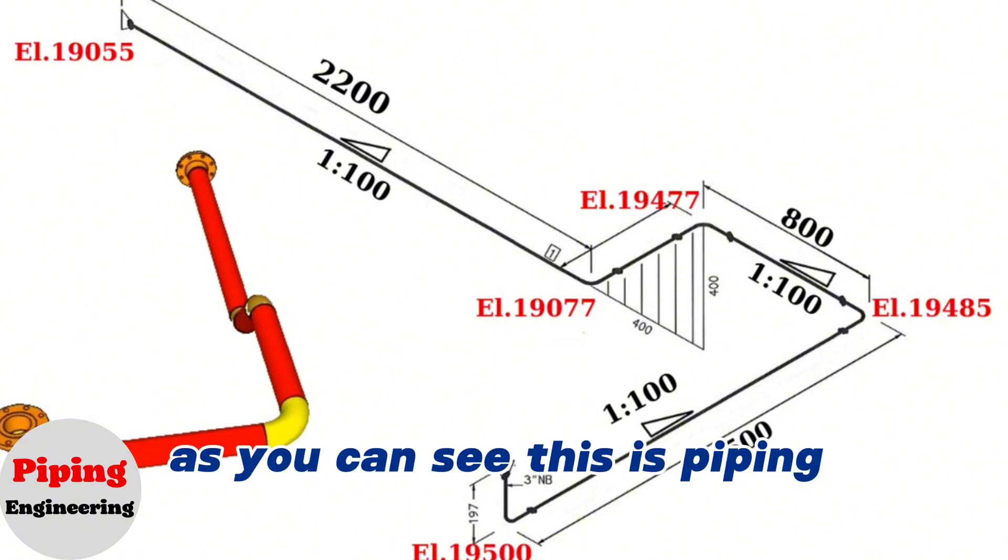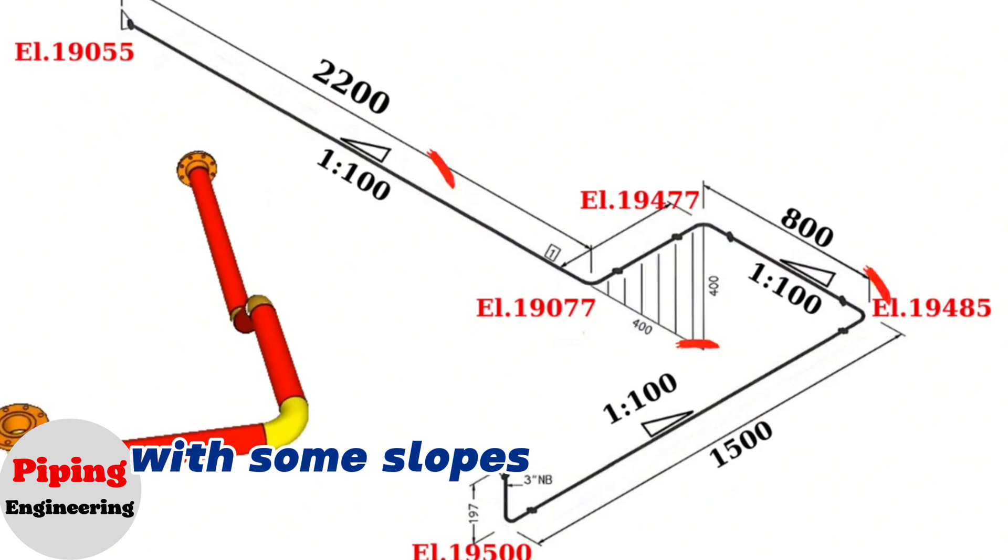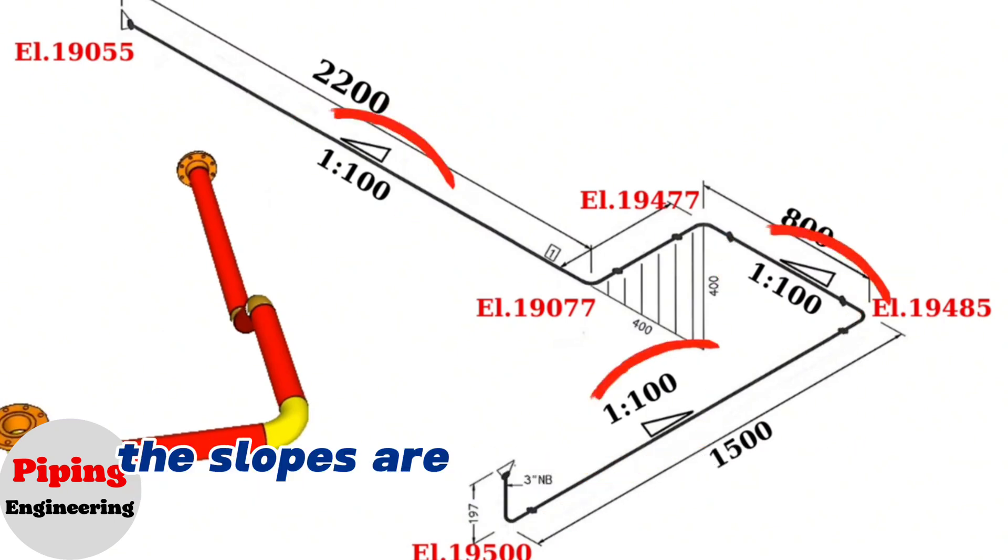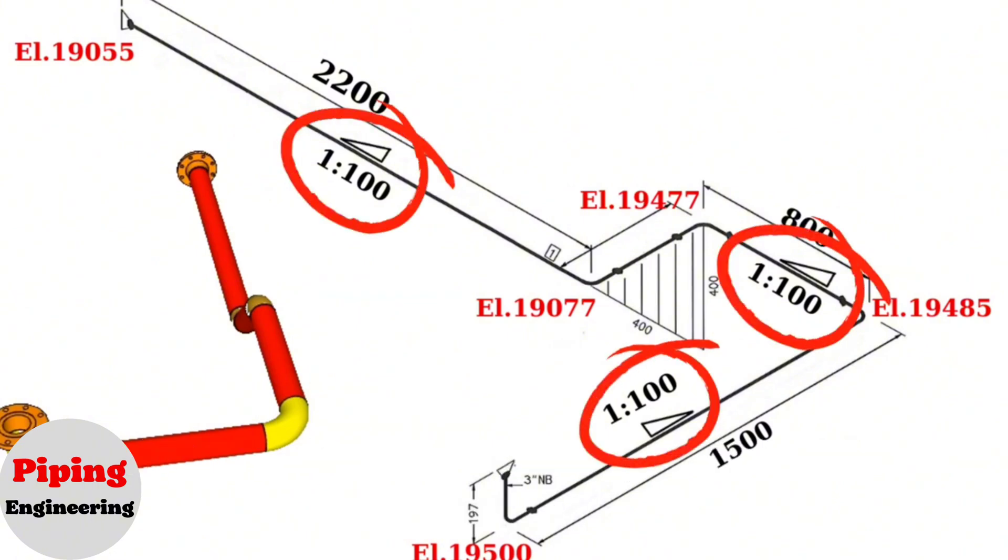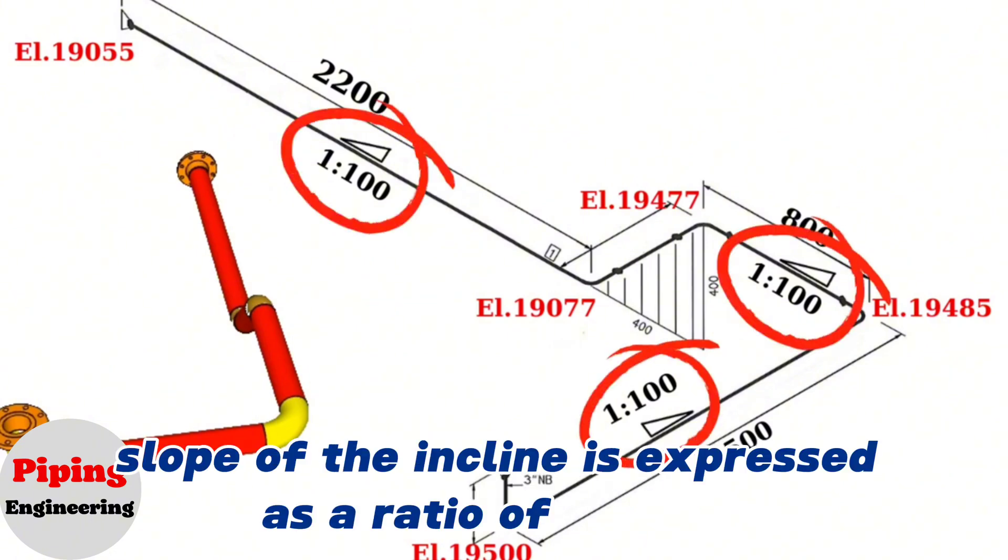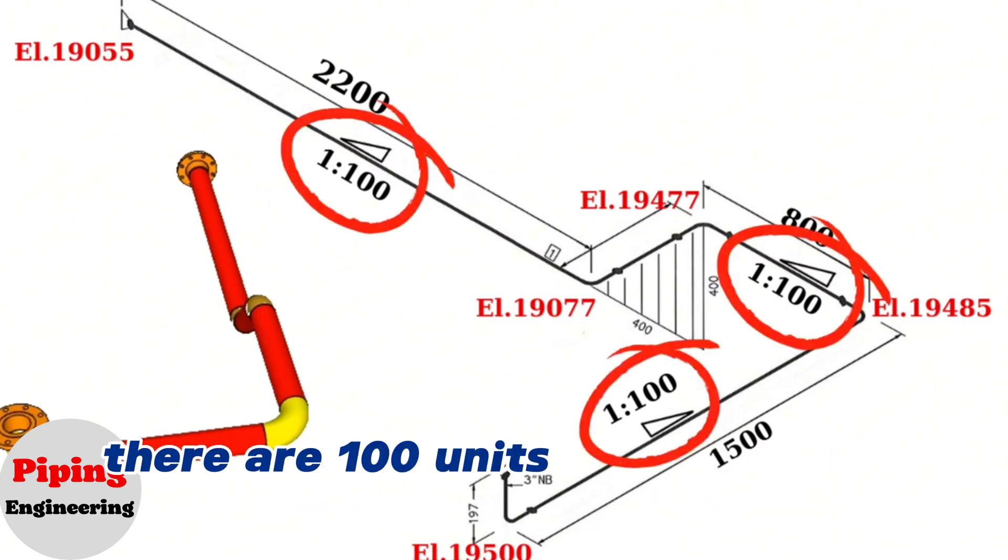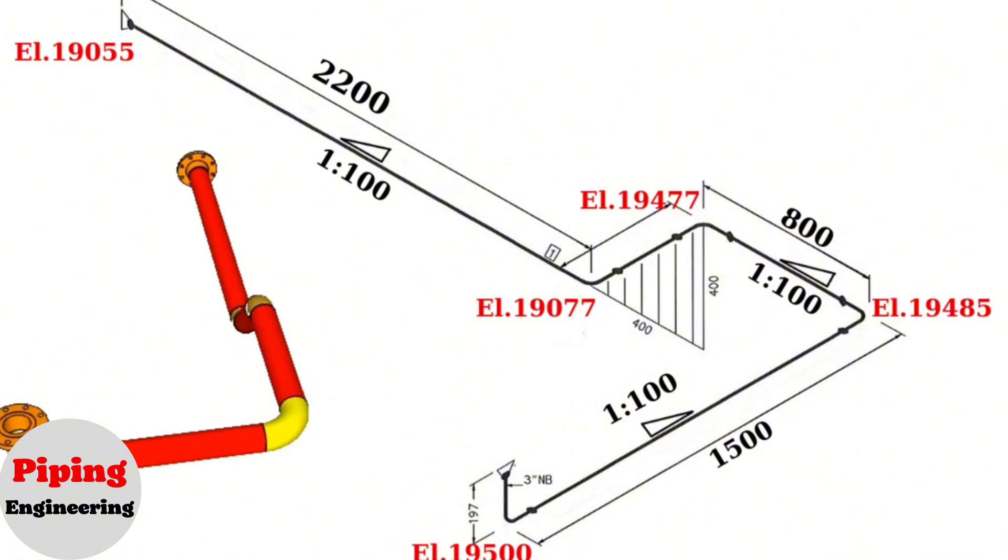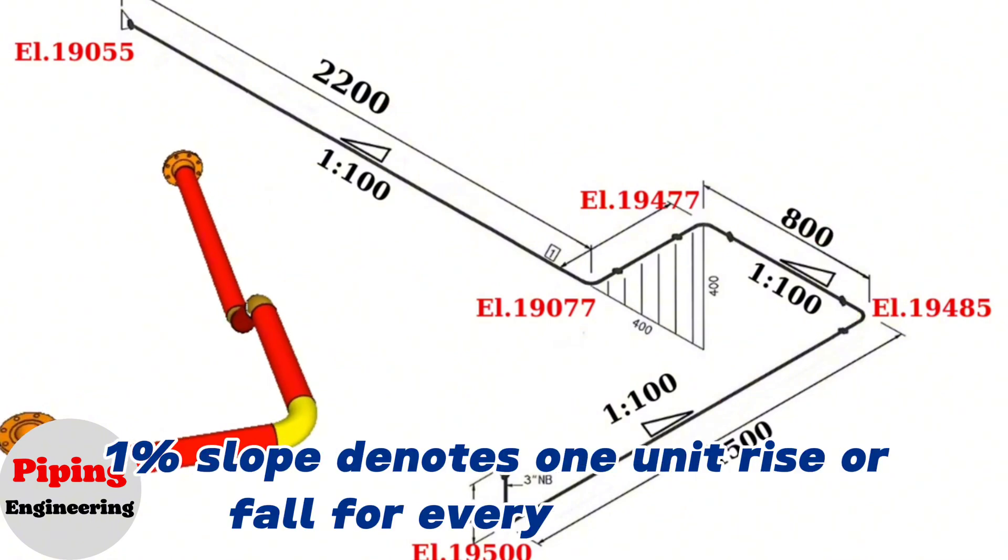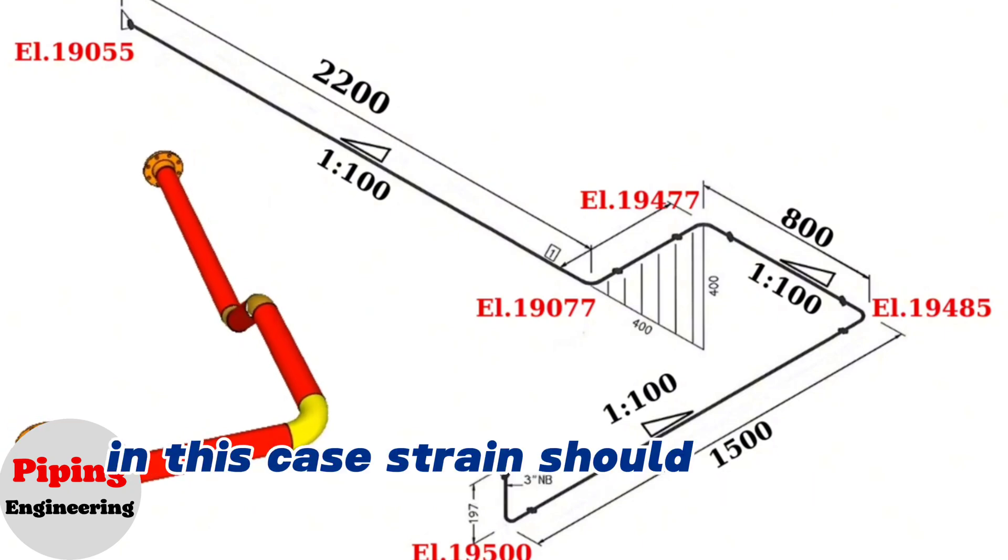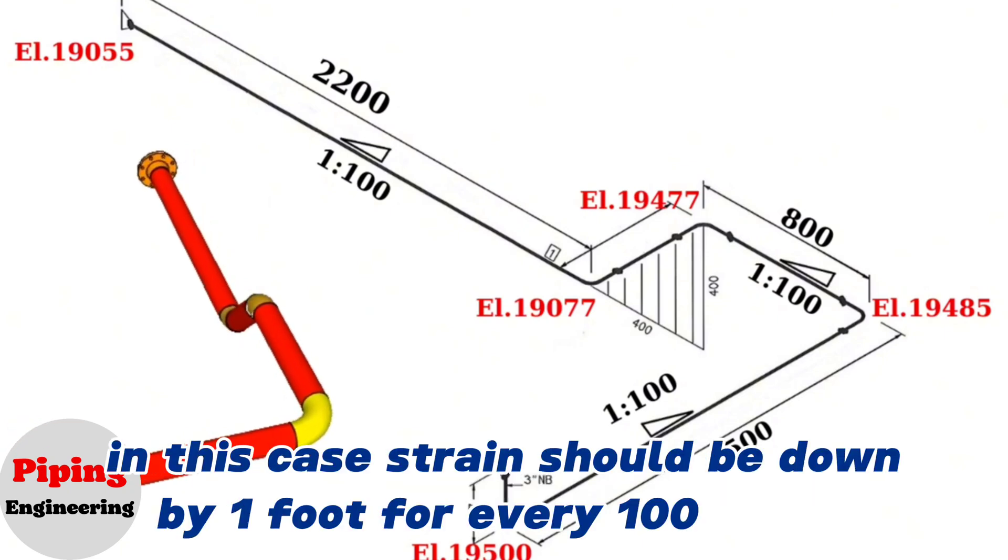As you can see, this is a piping isometric drawing with some slopes and different elevations. In the piping isometric drawings, the slopes are shown with this symbol. In this drawing, slope of the incline is expressed as a ratio of 1 to 100, meaning that for every one unit of vertical elevation there are 100 units for horizontal distance. 1% slope denotes one unit rise or fall for every 100 units horizontal length or distance. In this case, drain should be down by 1 foot for every 100 length.